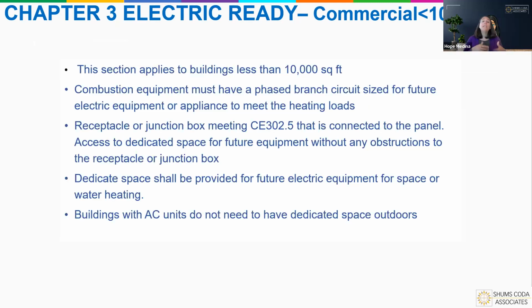So as you can see, I think this makes it a little bit easier to look at. Your combustion equipment has to have a dedicated branch circuit, sized for the future. You've got to have that receptacle and junction box, and all of that needs to comply with 302.5, which we haven't hit yet. Then it has to be connected to a panel, and there has to be access to a dedicated space for any future equipment. That means there can't be any obstructions, not only to that equipment, but to that receptacle or junction box, right? Because I think we've all had that issue. Who put that there? We don't want to have the conversation of who put that there. That's a useless spot. We can't ever get to that. So that's what they're trying to accommodate here.